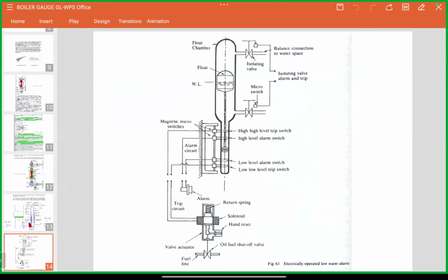A gauge glass doesn't give an alarm by itself. So in addition to the two gauge glasses, the boiler is required to be fitted with some means of level indicator that is also able to generate an alarm.